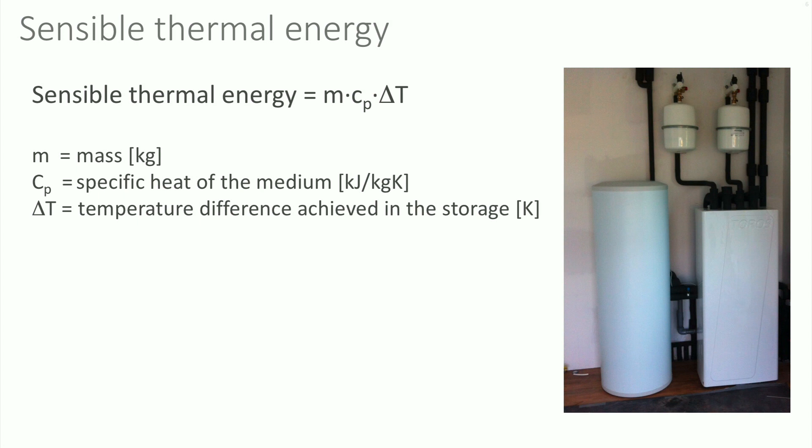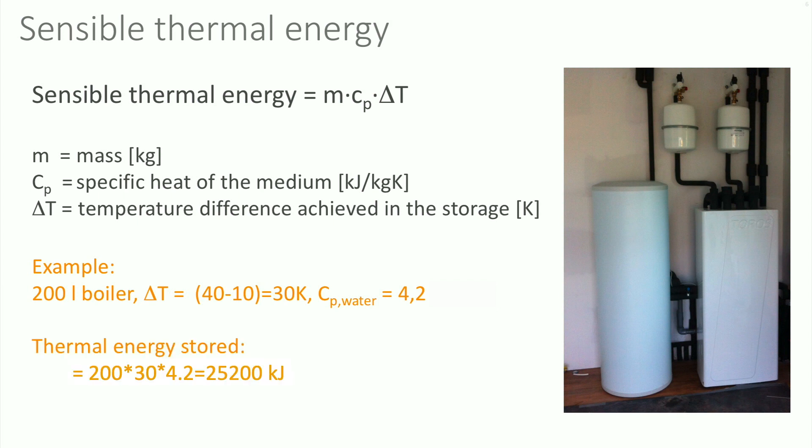The boiler has a volume of 200 liters and the temperature is raised with 30 degrees Celsius. The specific heat capacity of water is 4.2 kJ per kg·K. The thermal energy stored is thus 200 times 4.2, which equals 25,200 kJ.